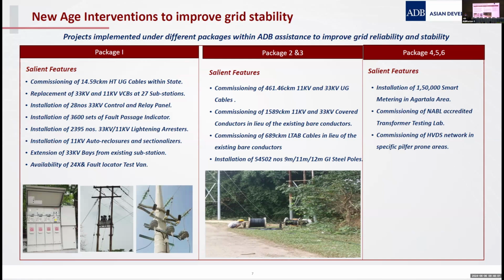Beyond going underground, we are planning ring-main features by introducing RMUs into the system, which will increase supply reliability and redundancy and improve safety. We have also introduced fault passage indicators and auto recloser sectionalizers as part of distribution system automation.